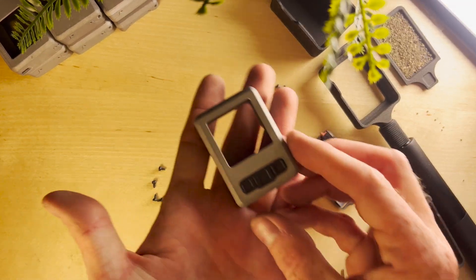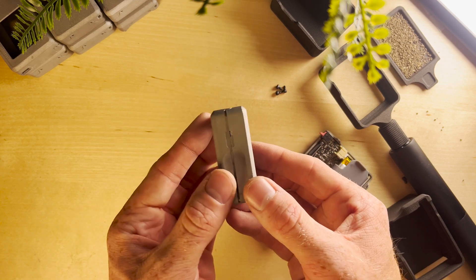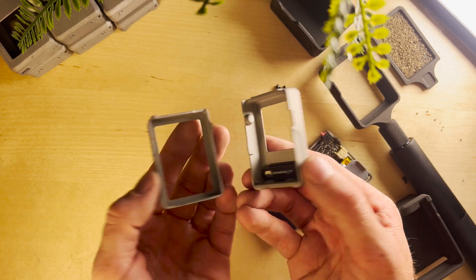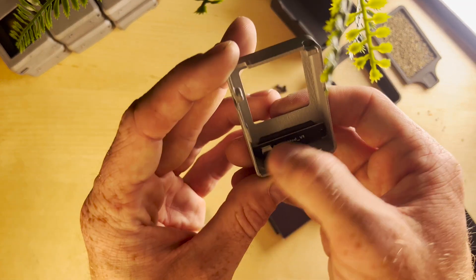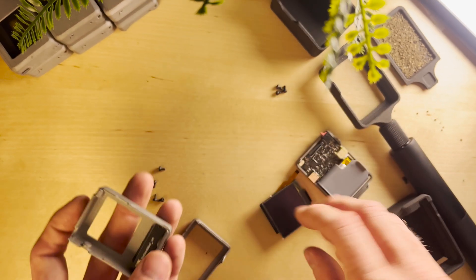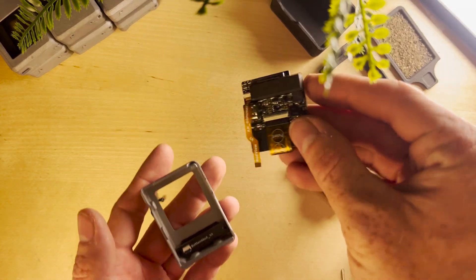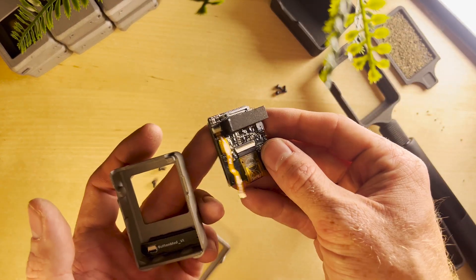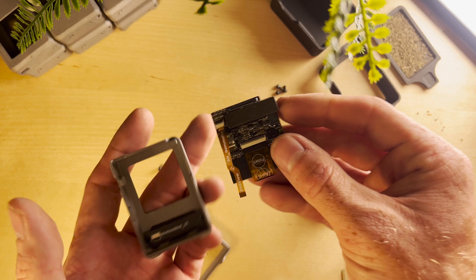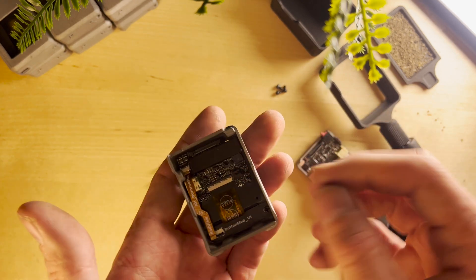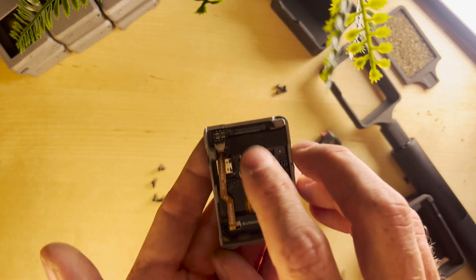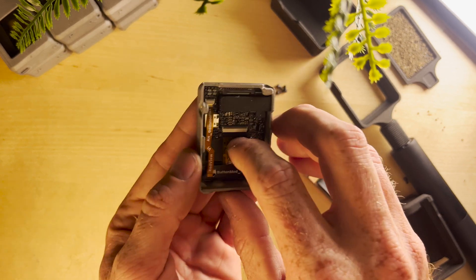Once we have all the screws out of our Gamma Mod, we're going to open it up so you can see the new PCB right here for our buttons. We're going to take our new scintillation crystal and display and we're going to drop it in just like that. This is our display but it also has that new scintillation crystal on it.